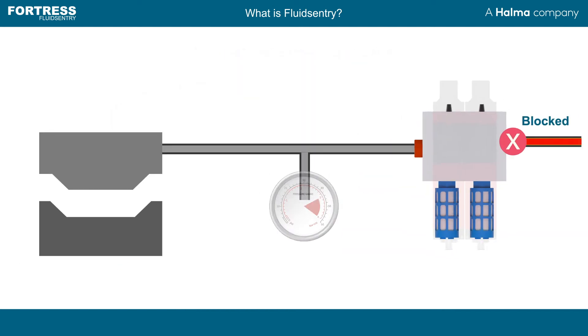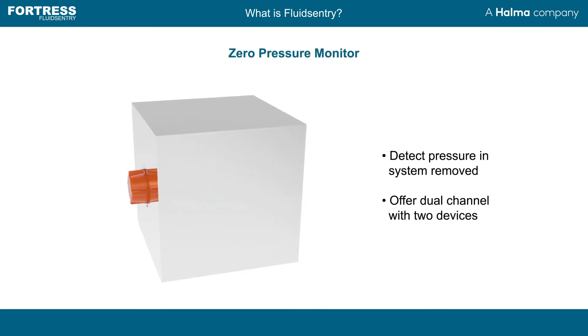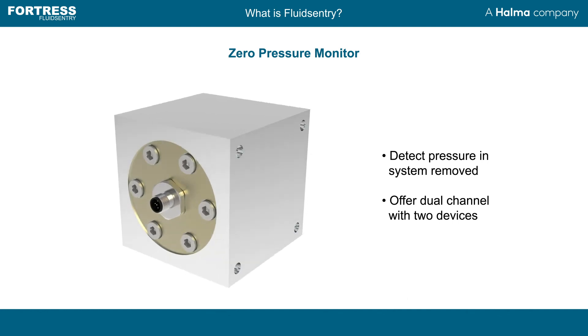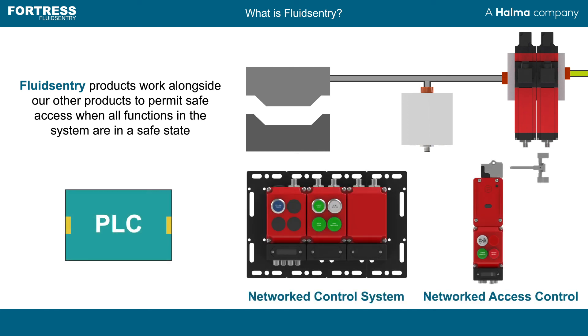Gauges allow local indication of pressure status, but how does your control system know when zero pressure has been detected? With a Fortress Fluid Sentry zero pressure monitor, we can provide positively driven single or dual channel contacts to detect when atmospheric pressure is achieved. Fortress Fluid Sentry products can be hardwired or work alongside our networked range of products to communicate over Profinet or Ethernet IP using the ProfiSafe and CIP safety protocols.